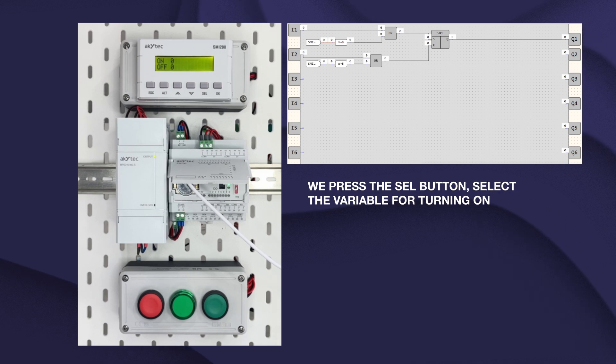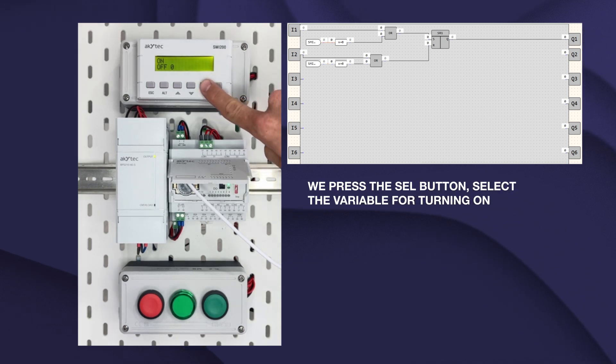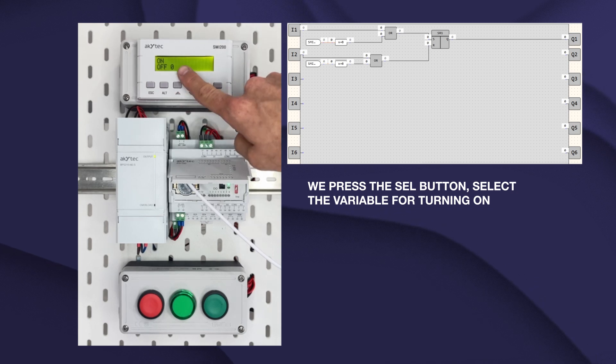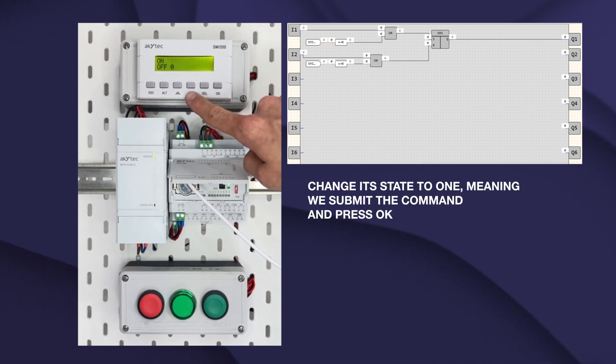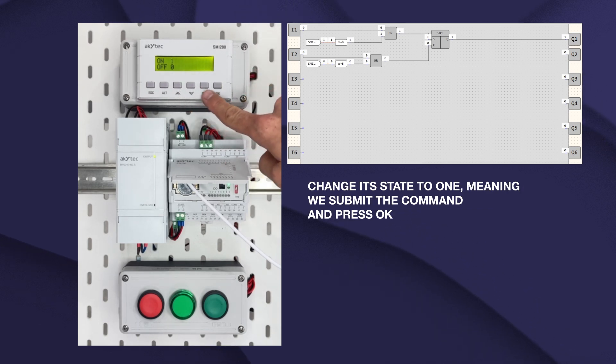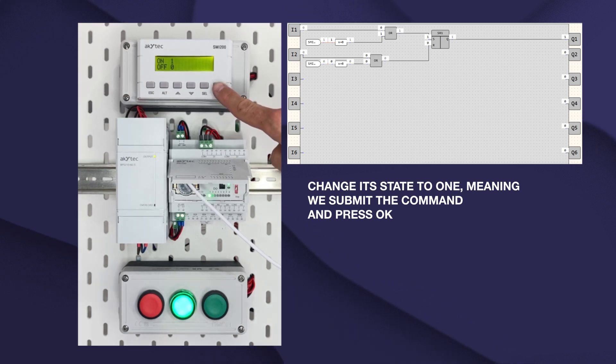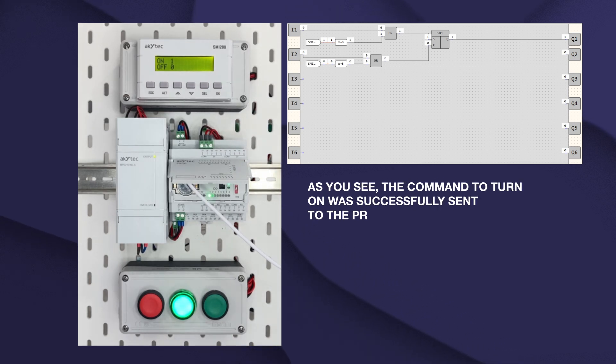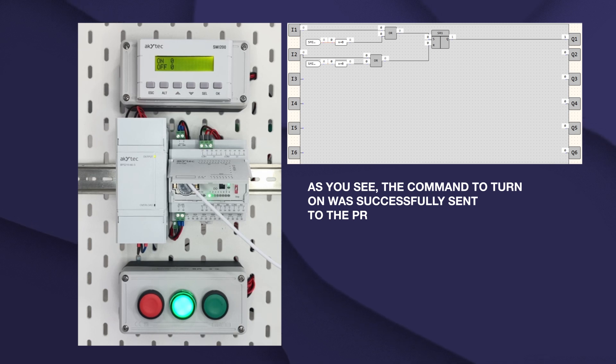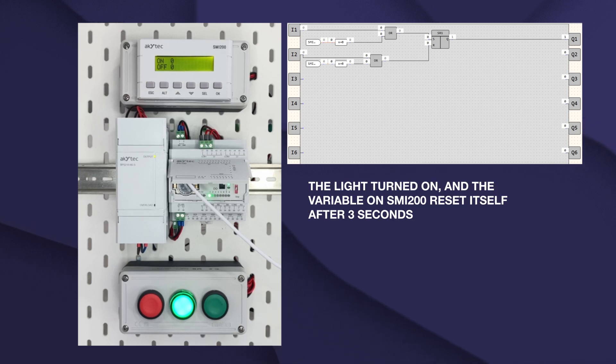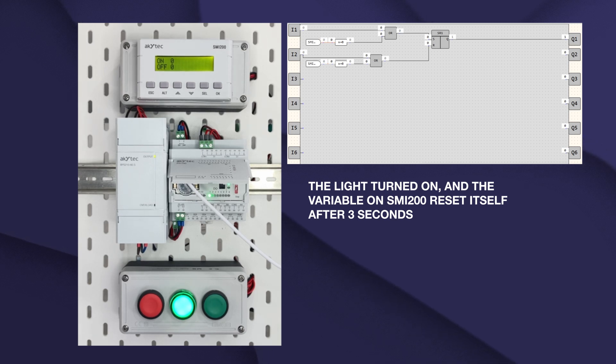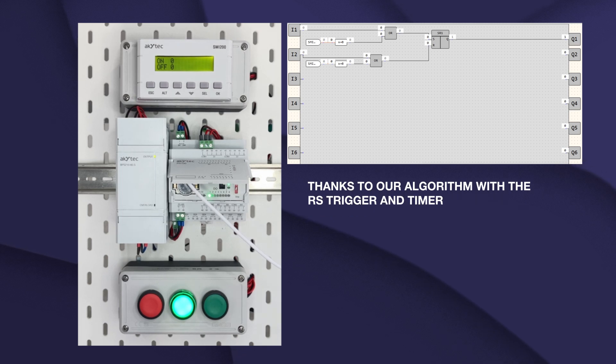We press the SEL button. Select variable for turning ON. Change its state to 1, meaning we submit the command and press OK. As you see, the command TURN ON was successfully sent to the PR. The light turned ON and the variable on SMI200 reset itself after 3 seconds, thanks to our algorithm with the RS trigger and timer.